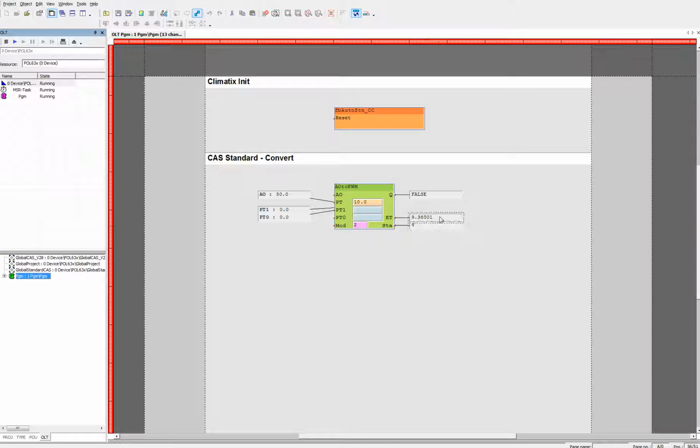So off, now on again, state is on, now state is off. In case that we use a limitation for minimal valid time on, it means that if we are not able to satisfy the minimal valid time for on, the output remains in off state. Let's try it. If I put there 6 seconds, the condition for minimal time to be on is not possible, so in the next PT time it will remain in false state.